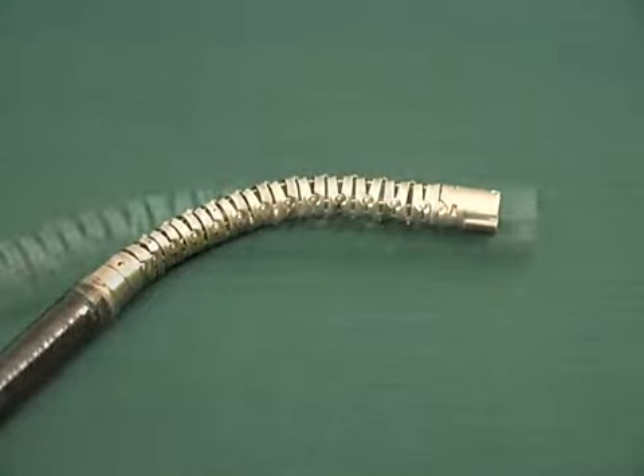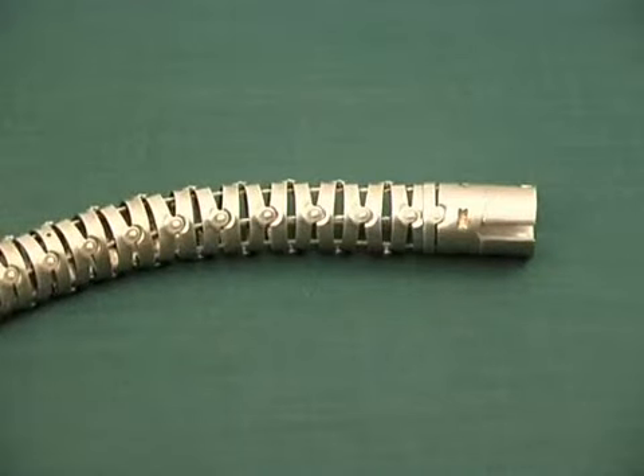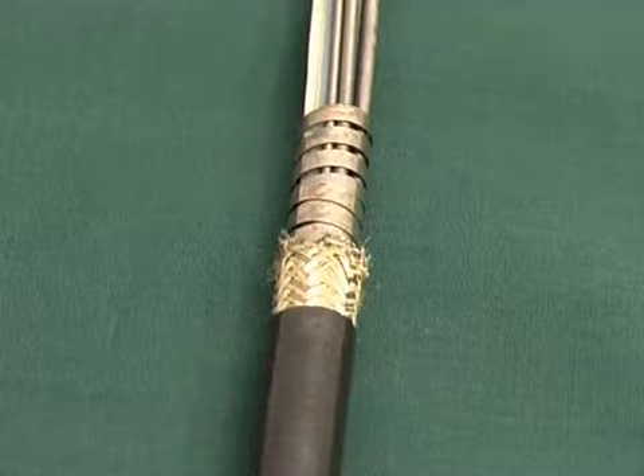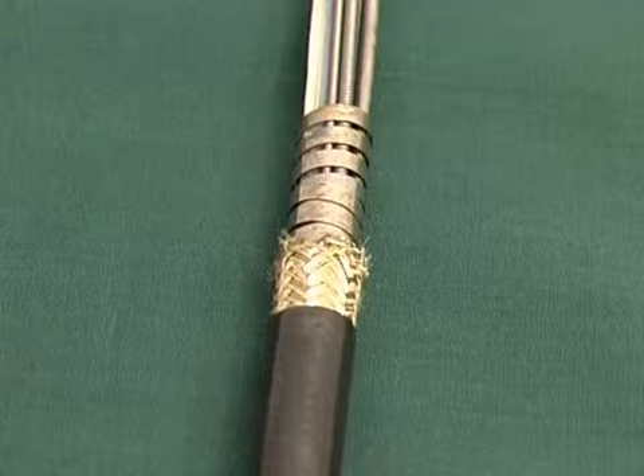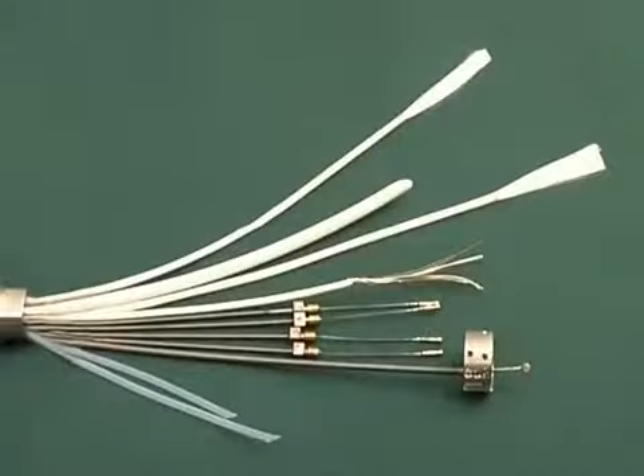This is the bending section of a colonoscope. Inside the bending section there are 4 pull wires. They work a bit like the reins of a horse. Pulling on one wire angulates in the chosen direction. The insertion tube, or shaft, is complex and tightly packed. Inside, as well as the electrical connections, are 2 light bundles, air and water channels, the biopsy and suction channel, and the 4 angulation wires.